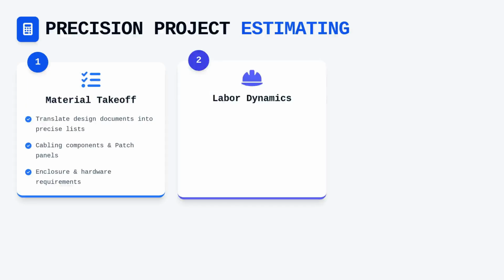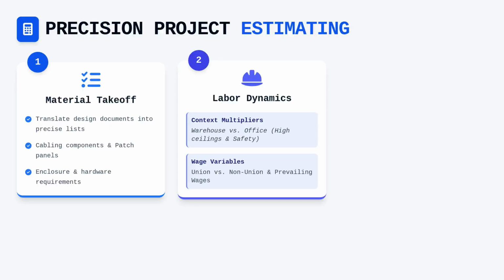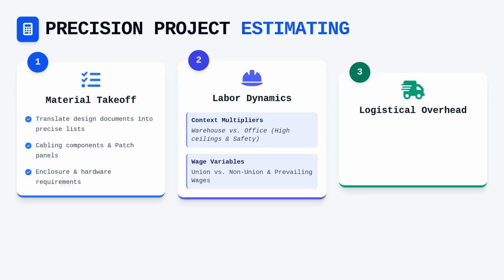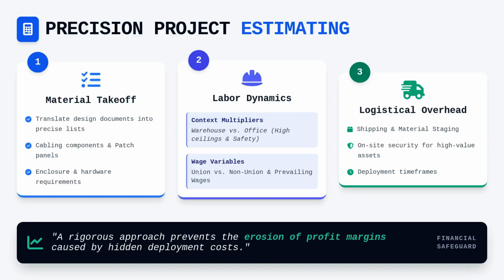installation. When calculating labor units, you must move beyond simple industry averages and apply context-specific multipliers to reflect the actual environment. For example, installing category cables in a high-ceiling warehouse or a confined space requires significantly more man-hours than a standard office build-out due to the added difficulty of access and safety compliance. You must also account for the nuanced differences in labor costs, such as the gap between union and non-union rates, as well as the mandate of prevailing wages on public projects. Factor in the logistical overhead of shipping, material staging requirements, and the necessity of on-site security for high-value components before installation even begins. By maintaining a rigorous approach to these variables, you prevent the erosion of your profit margin caused by the common hidden costs of project deployment.